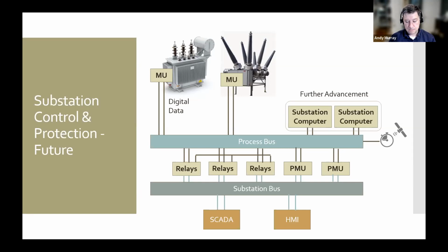But it's also been looked at as a way of catching potential cyber attacks. If someone was able to get onto this process network and wanted to make that transformer or device start to misbehave, one of the best things you can do is fake the data, so SCADA or the people watching have no idea it's actually happening. The idea here is that with some of this analysis at the process bus level, they'll be able to see that something's not right because the math doesn't add up, and catch those occurrences that way.